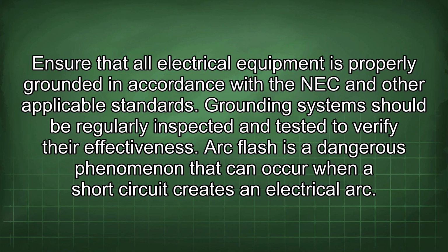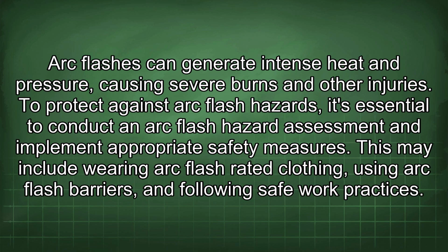Arc flash is a dangerous phenomenon that can occur when a short circuit creates an electrical arc. Arc flashes can generate intense heat and pressure, causing severe burns and other injuries. To protect against arc flash hazards, it's essential to conduct an arc flash hazard assessment and implement appropriate safety measures. This may include wearing arc flash-rated clothing, using arc flash barriers, and following safe work practices.